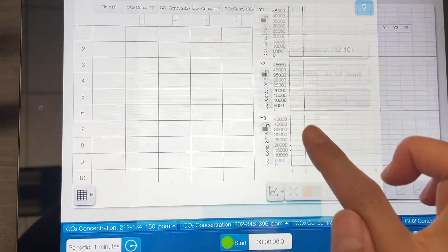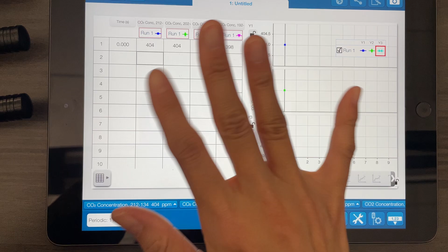Click on the green button that says Start, and it's going to start reporting the reading. Notice that all the beginning numbers are somewhere close to the 400 range, so we have a reasonable range there. And let it run for about 4 minutes until the CO2 reading stabilizes. Since our CO2 probes are quite sensitive, the reading will never be the same, but it will stabilize to a reasonable extent. It's not going to go up and down too crazy.